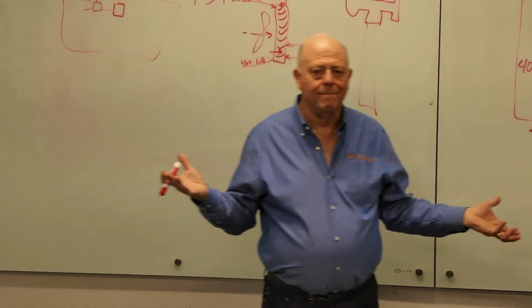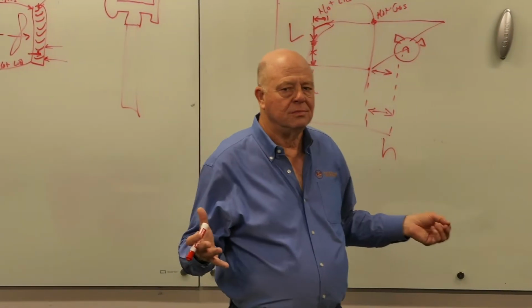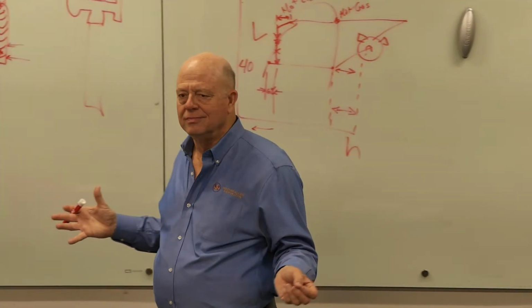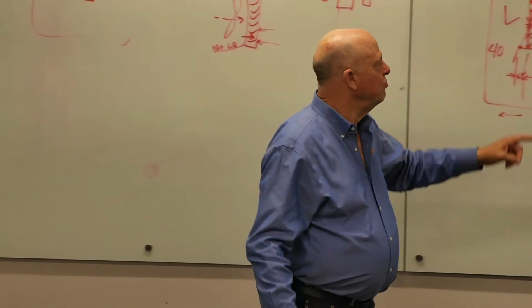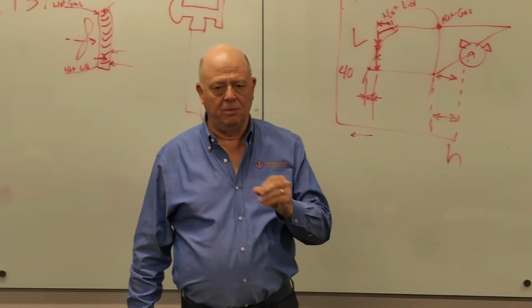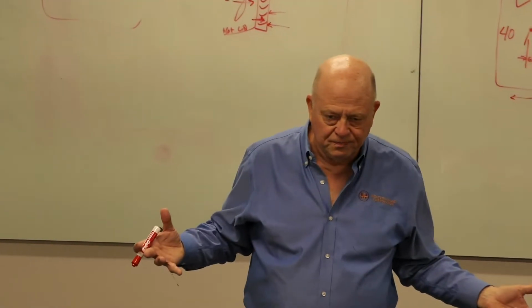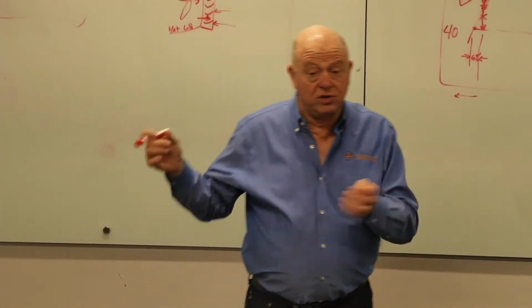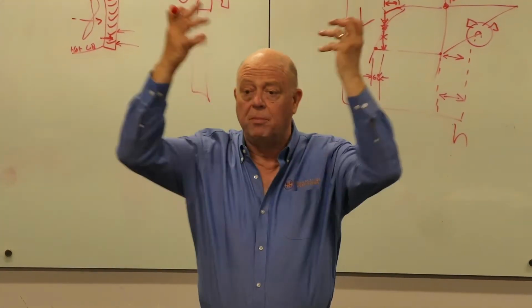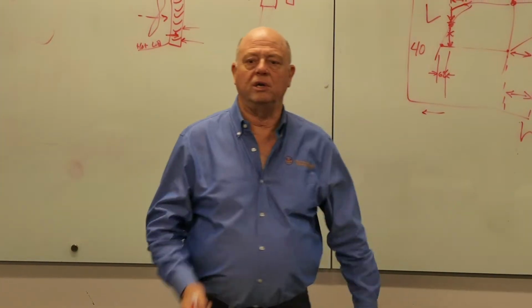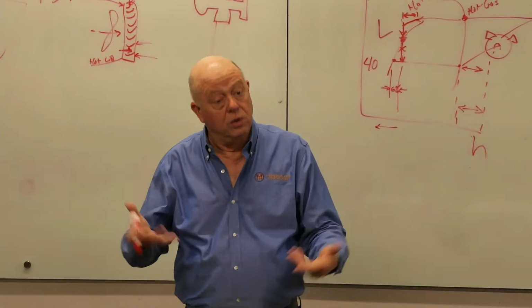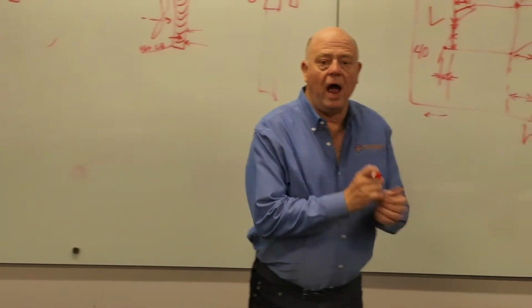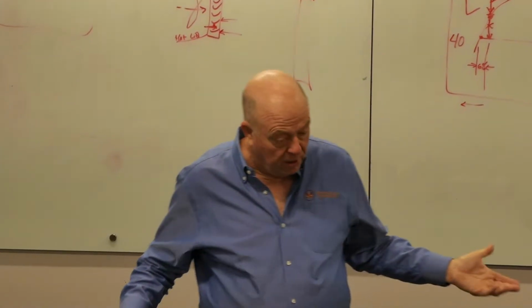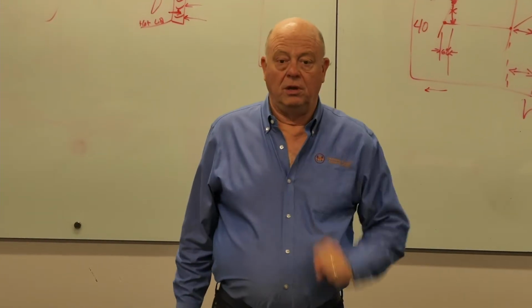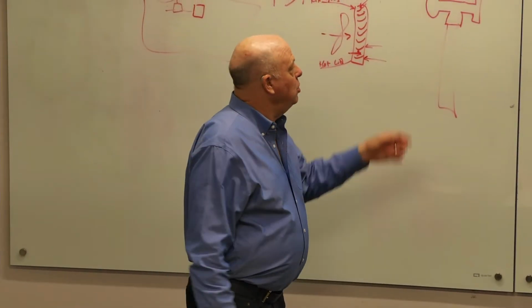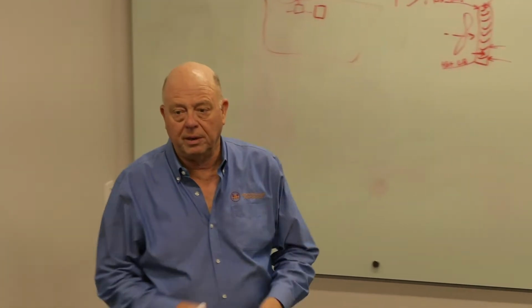It affects the other side of the cycle. That's one reason. You need some of that refrigerant to come back to cool the compressor. There's a motor in here, an electric motor. It's a hermetic motor, cooled by that refrigerant gas. The first thing that happens when the gas enters the compressor is it runs over the motor windings. Then it goes to where it's going to be compressed. If it gets too warm, it won't adequately cool the motor windings. I would have guessed their maximum would have been more like 40, but Copeland knows more than I do. 50. So in theory, you could operate up to a 50-degree superheat. I wouldn't recommend it, but you could.